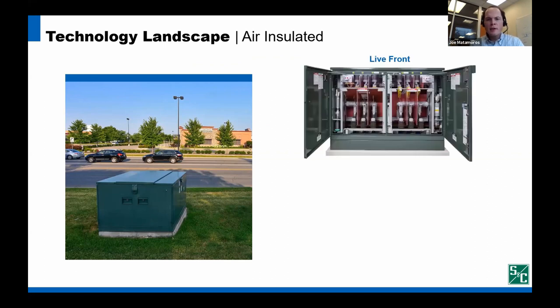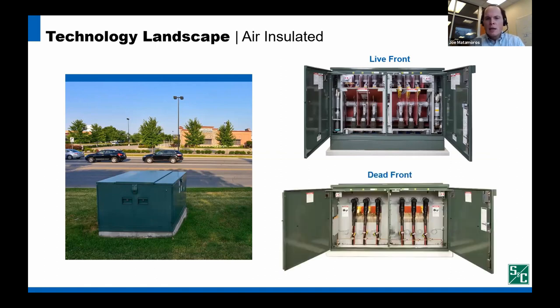There are two principal categories for air insulated gear. Live front gear was the first generation of air insulated pad mount underground distribution switchgear. As you can see, as I highlight with the laser pointer, cables are terminated directly in the gear. And when the door is open, the gear front is live. To reduce operator exposure to voltage and to improve cable handling operations, dead front gear evolved later. As I'm highlighting here, the cables are terminated with separable connectors. This presents the operator a dead front when opening the doors. For both live front and dead front gear, the fact that we're using air insulation enables high visibility to the active components of the gear.